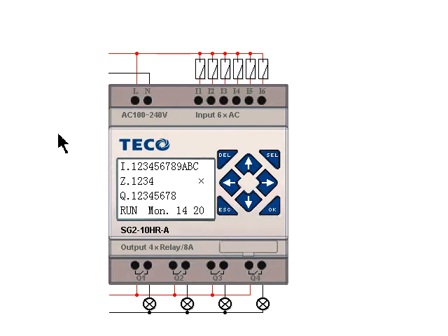There is no way to reset the no load alarm because you never want the loader trying to load material when there's no material. So the only way to resolve that issue is to have it load material or to turn it off until you can fix the Gaylord. We'll put it on again, and it's loading number 1, and within 10 seconds you'll see that no load alarm come on output number 4.